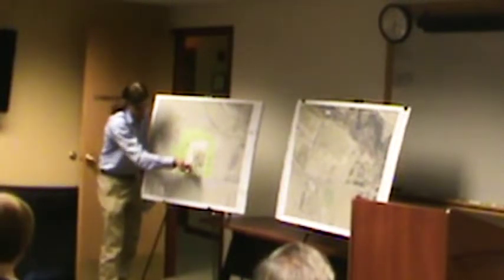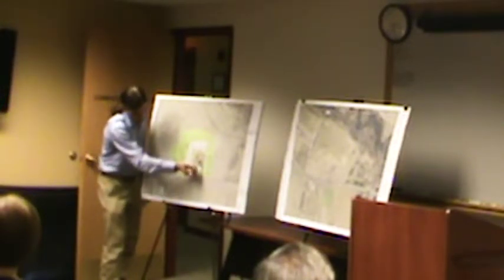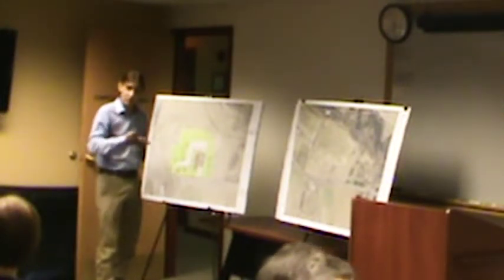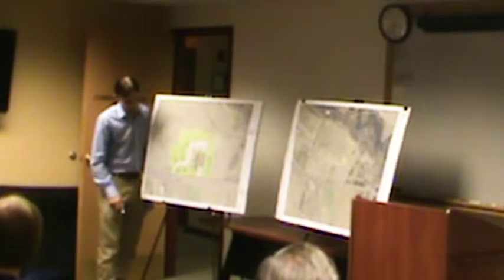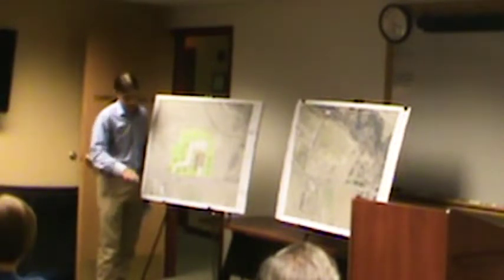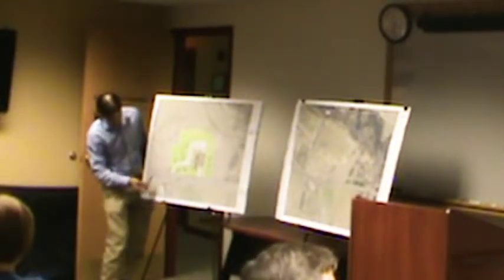Sewer-wise, because we have a drain in the middle of the apparatus bay, and there could be the possibility of oil or grease coming off of the trucks, we would have a drain that then goes to what we call a grease and water separator, similar to what you would have in a restaurant for the grease trap, but in this case, it's really not for that amount of grease. It's really for any oils or anything that comes off of the engines from any of the vehicles or from the work there. We're showing it right now, preliminary, as a small tank so that it has access. That tank has to be drained a certain number of times. Actually, when the levels of the oils get to a certain height, a service comes in and pulls the oils out. And then from there, we're also showing a 6-inch sewer line that would then hit a manhole.